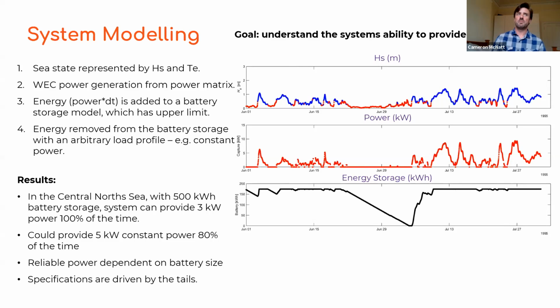The amount of power it can provide really depends on the battery size—the more battery you have, the more energy storage to ride out long periods of no power generation. So the specifications for this system are really driven by the tails, meaning the extreme conditions. This modeling was over 20 years of data, and in that time the amount of time the system would fail was very limited—it wouldn't even happen every year.